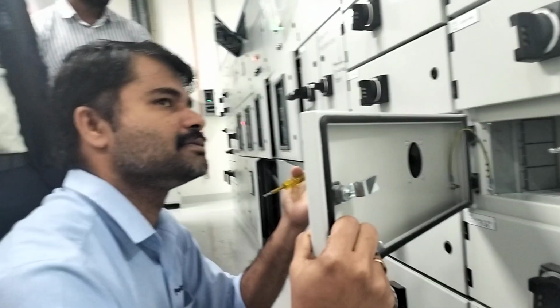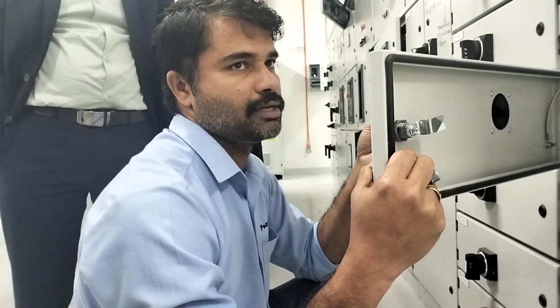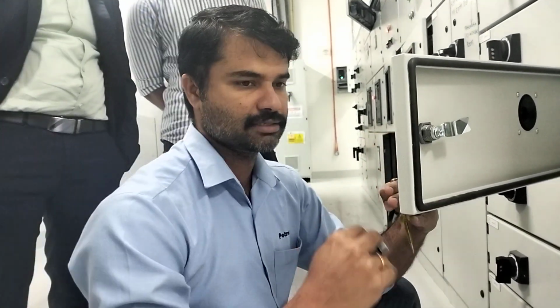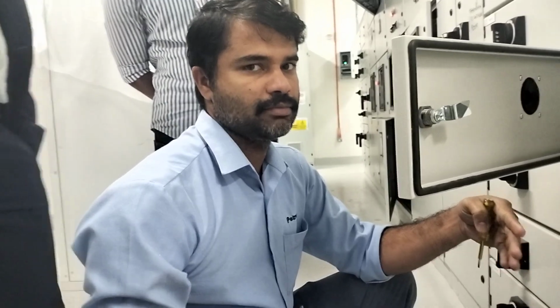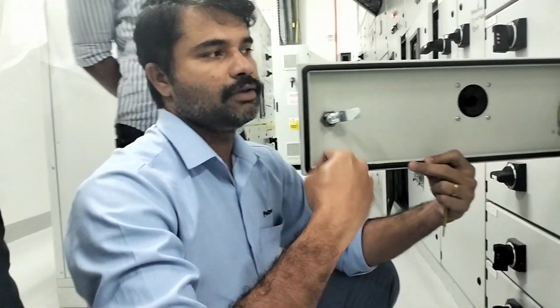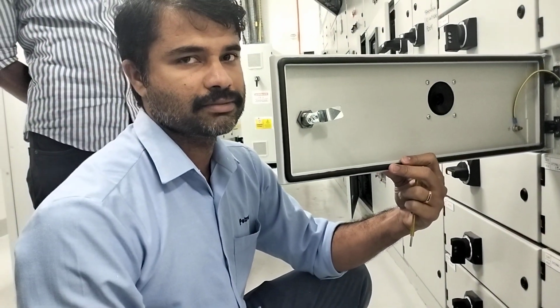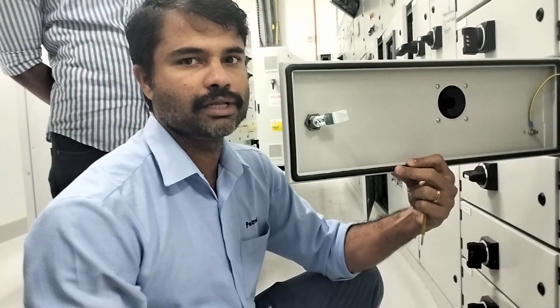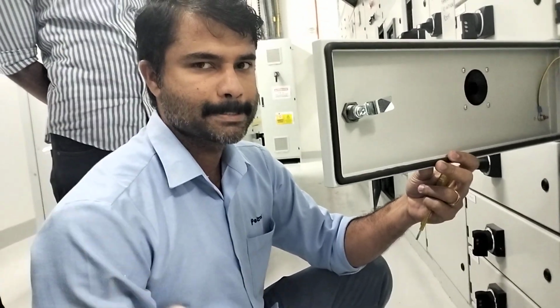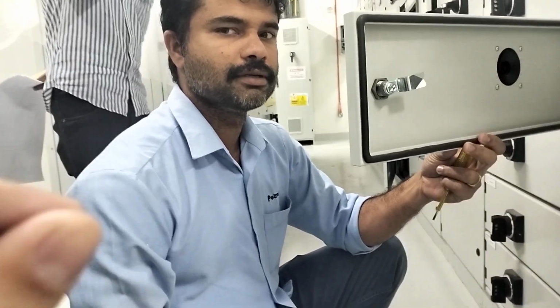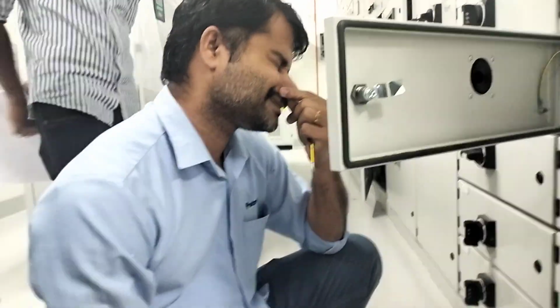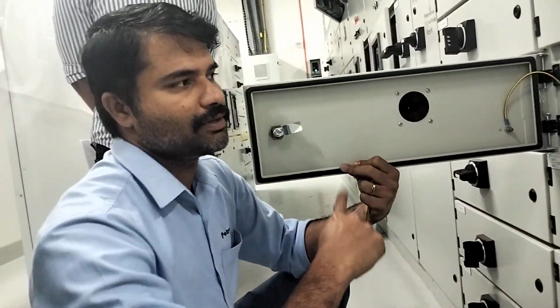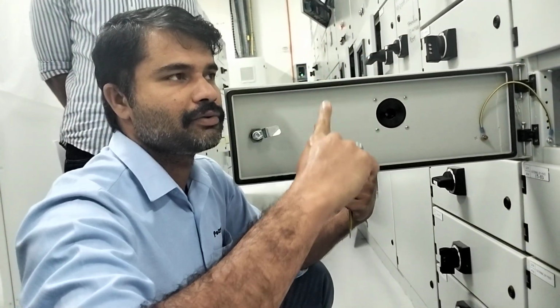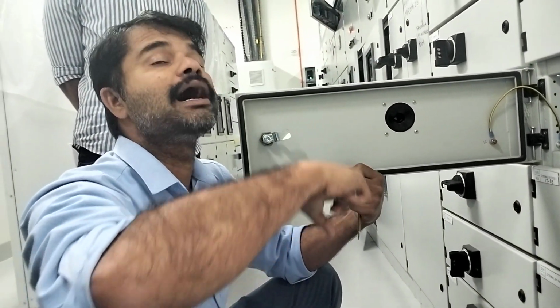If long, let's say I am testing some breaker, you can see the breaker might trip based on my selection around 30 seconds, 40 seconds, 50 seconds, depending on the ground. If I am going to the instantaneous phase, it will trip in milliseconds. Yeah, that's why I'm telling you. Instant means immediately trip. Long time means you give some allowance time. Everything will be defined based on your graph and your ampere.